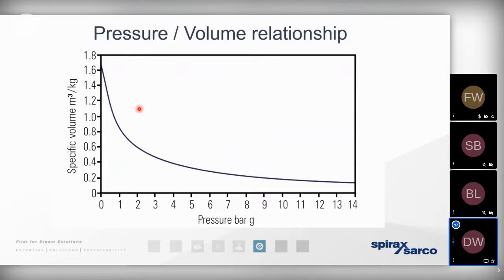We know if we've got a kilogram of steam existing at 10 bar gauge, it occupies a very, very small volume. Whereas if we've reduced the pressure of that steam, say downstream of a pressure reducing valve, then because there's nowhere near as much compression on that steam, it's going to exist at a much, much greater volume. In the example of a kilogram of steam at 0 bar gauge, its volume is approximately 1.673 cubic meters. So it really emphasizes the benefit of distributing steam at the highest possible pressure.